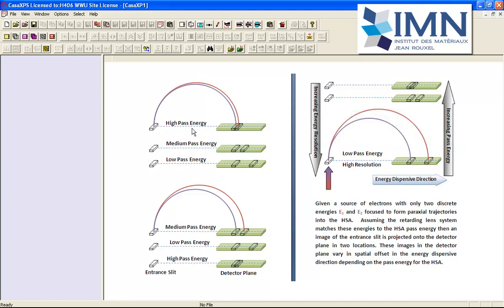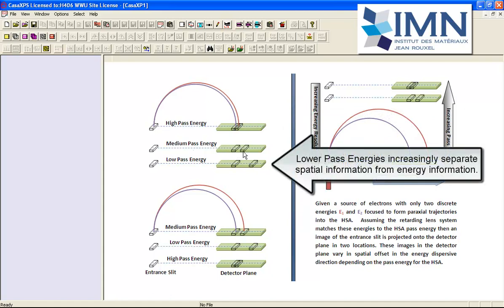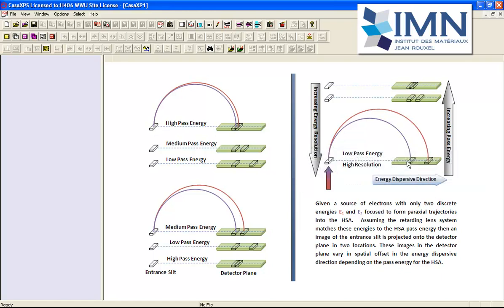As we decrease the pass energy, we increase the resolution because the image of this entrance slit moves apart. In this case we've got pass energy 10 where there's a significant separation of these images, so we get a peak that is well resolved in terms of energy.